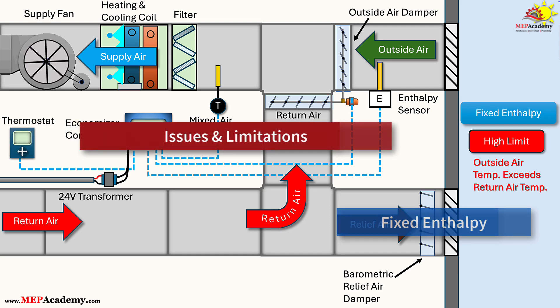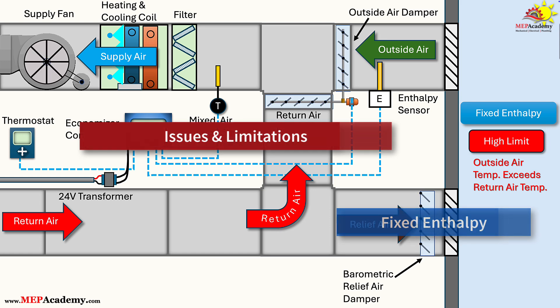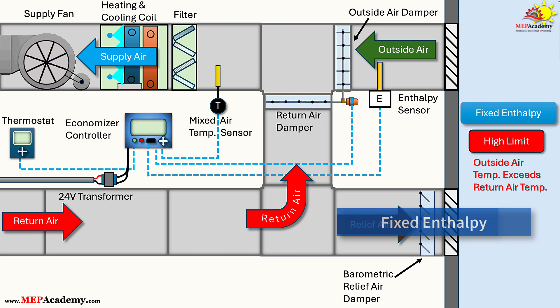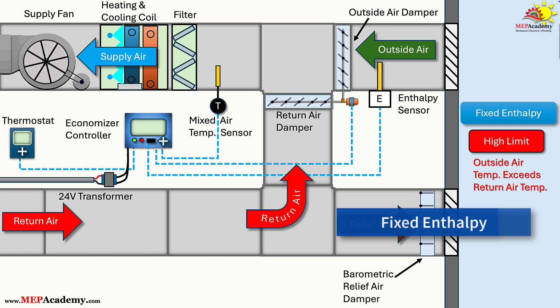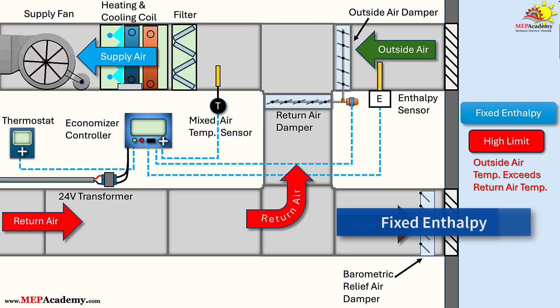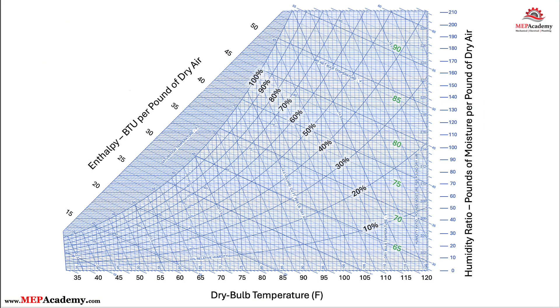Issues and Limitations. Despite considering humidity, fixed enthalpy has notable flaws. It can err by disabling the economizer in cool, rainy weather – high humidity but low temperature – missing cooling opportunities in cold climates. In dry climates, it might enable during warm, dry conditions, increasing sensible loads unnecessarily. Sensor inaccuracies are significant, ±2 BTU/lb, especially with humidity sensors that drift over time and require frequent calibration, leading to higher maintenance costs. Analysis shows it's often not cost-effective compared to dry bulb methods, with errors more pronounced in dry climates like Albuquerque, Zone 4B. Standards restrict it in dry, marine, or very cold climates, and it's generally not recommended due to added complexity without proportional benefits.